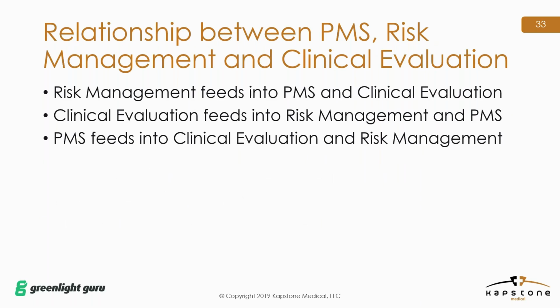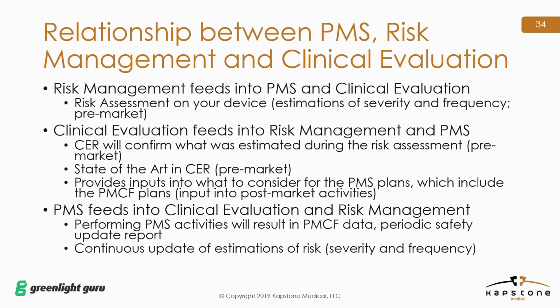So I'm going to make this really clear for you. Risk management feeds into post-market surveillance and clinical evaluation. Clinical evaluation feeds into risk management and post-market surveillance. And post-market surveillance feeds into clinical evaluation and risk management. I am being somewhat humorous here, but that is really what is required. They all feed into each other in some way.